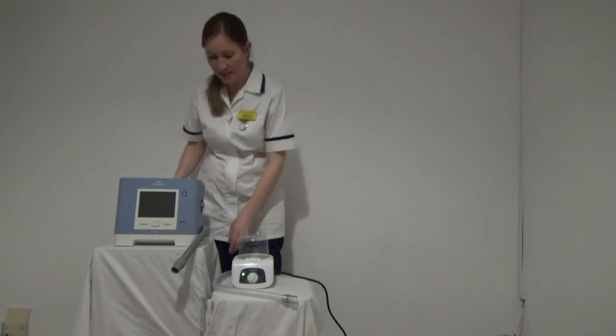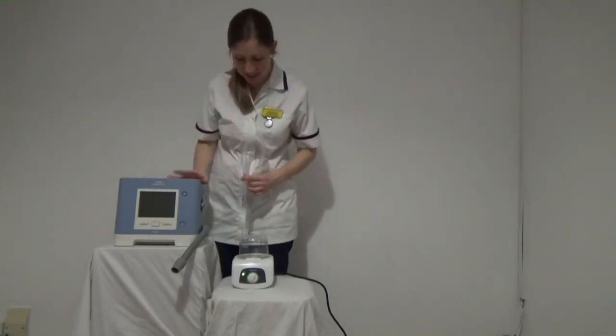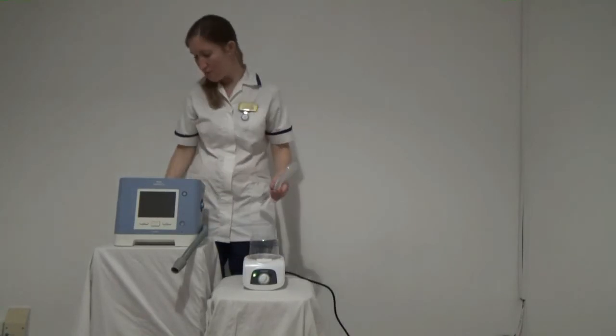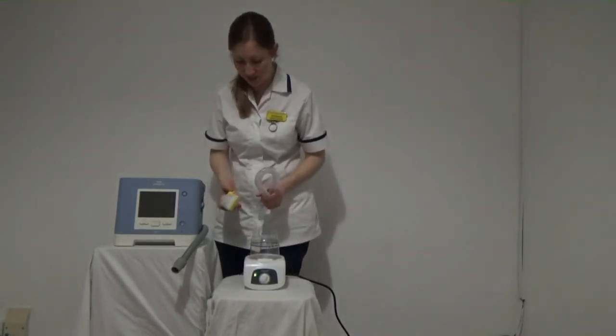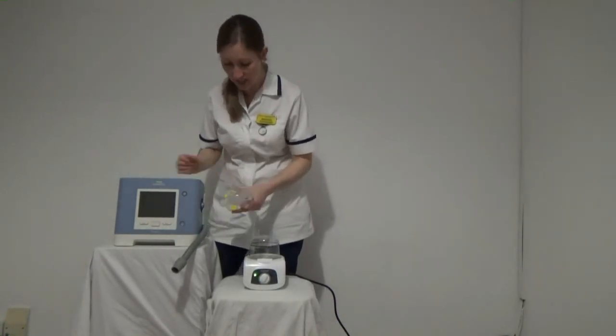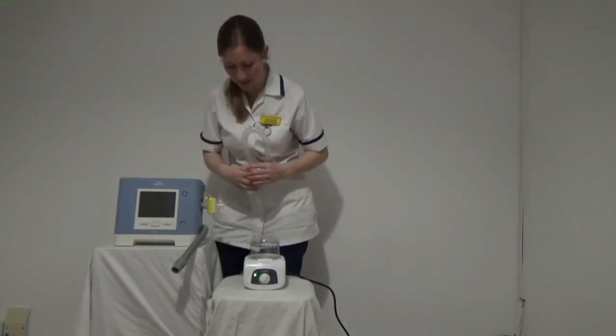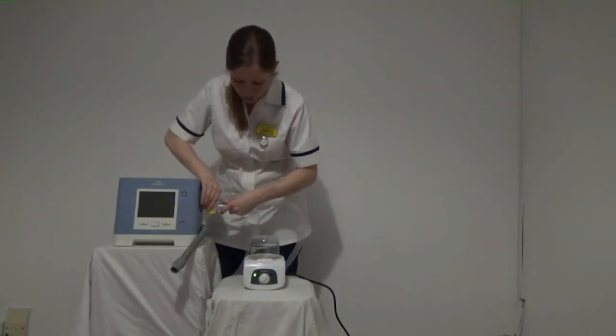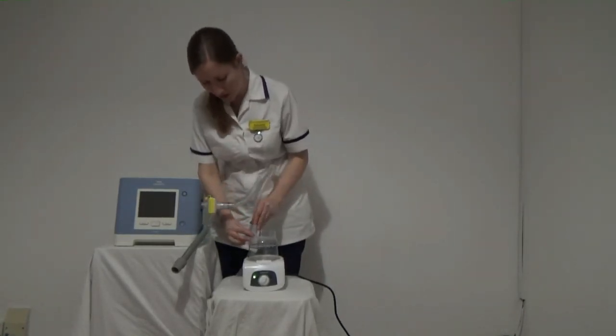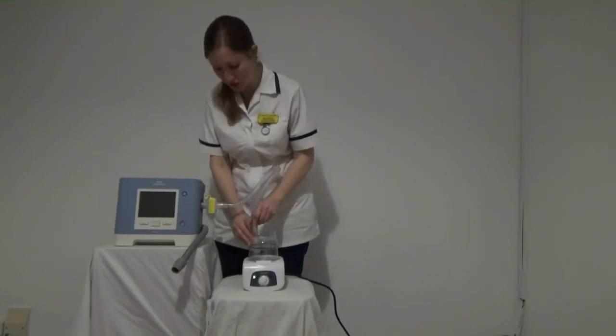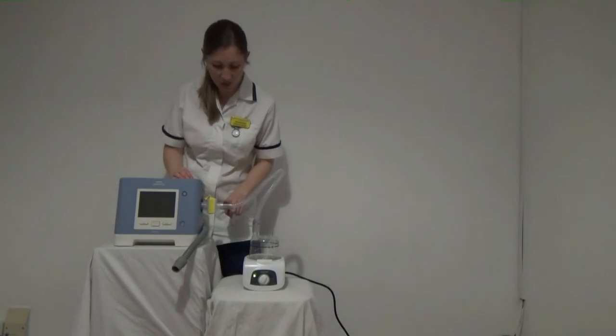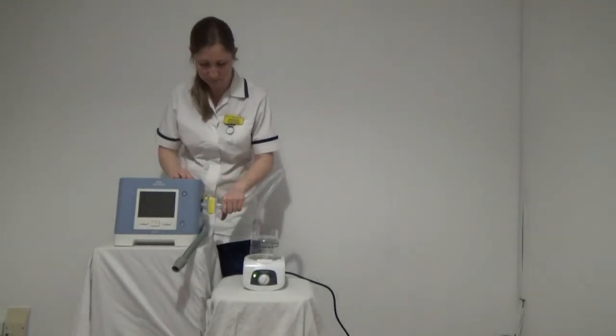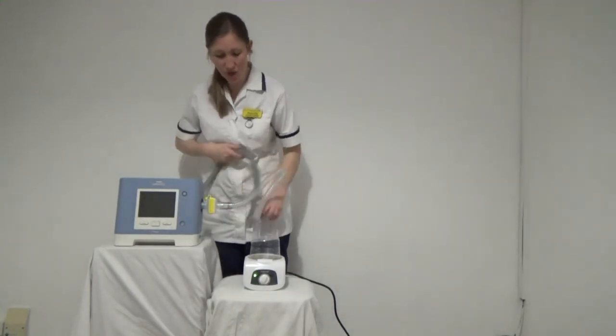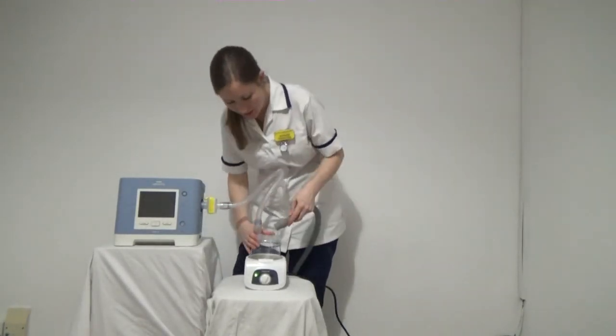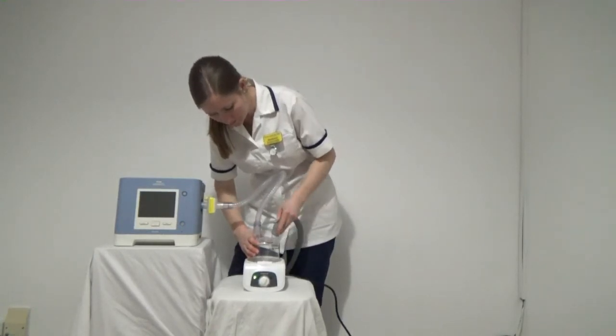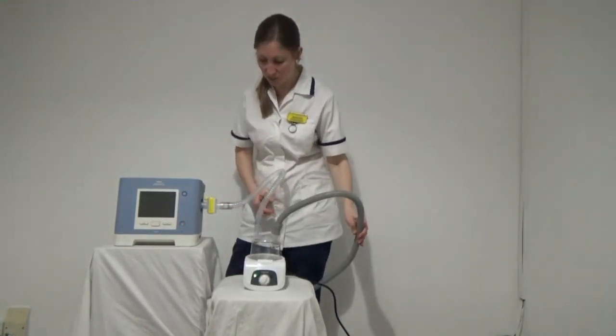Other equipment you will need is a short hose to connect the ventilator to the humidifier. You may or may not be advised to use a filter. If you are advised to use a filter, this is a yellow filter, and this would go into the side of the ventilator. Then the short hose connects onto there and then onto the holes. Again, it doesn't matter which hole you connect to. If you're advised not to use a filter, this hose would go straight onto the side of the Trilogy. Next, you need your long hose, which goes to your patient. This connects onto the other side of the hole, and this tube would then carry on to your patient.